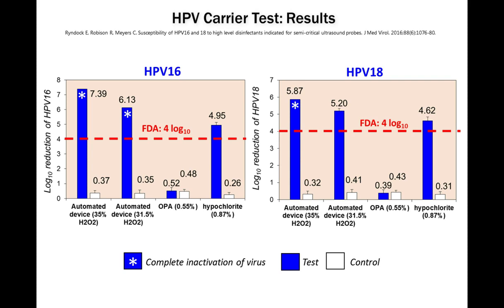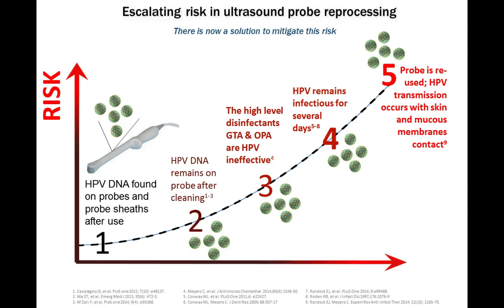HPV-18, again, similar to 16, could give greater than a 4-log reduction whether we use 35% or 31.5%, and OPA was unable to deactivate HPV, or hypochlorite, again, was able to deactivate or kill HPV at greater than a 4-log reduction. So according to this data, this automated high-level disinfection system was effective at deactivating or killing both HPV-16 and HPV-18.